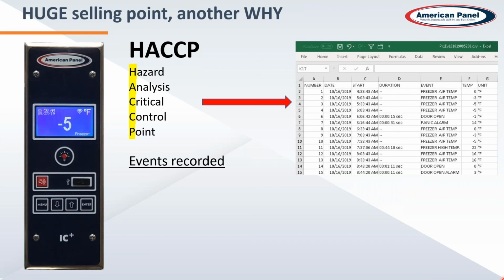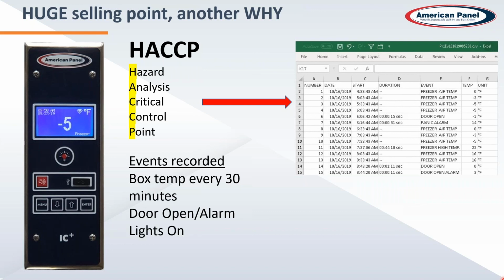Some of the events recorded by the system controller are going to be the box temperature every 30 minutes. The door open alarm, so you know when the door's open. If somebody's going in at all hours of the day or leaving it open for too long, you have a record of it. Lights on, anytime somebody turns the lights on, that's recorded. Panic alarm, if the unit's equipped with a panic, then it would record those panic events in the HACCP log.